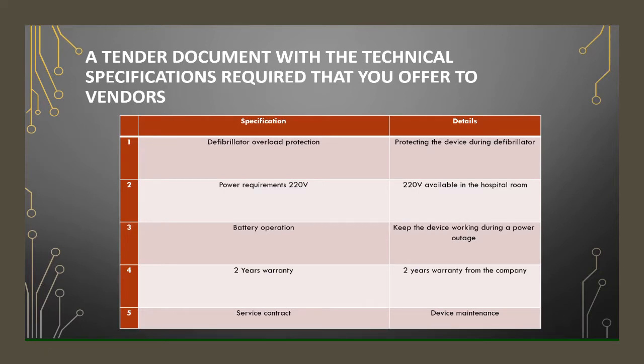In the tender document with the technical specification required, we listed the previous specifications and detailed them in this schedule. So in the first one, the defibrillator overload protections for protecting the device during the defibrillator, and the power requirements, 220 volt available in the hospital room. Battery operation, keep the device working during power outage. 2-year warranty from the company, and service contract for the device maintenance.